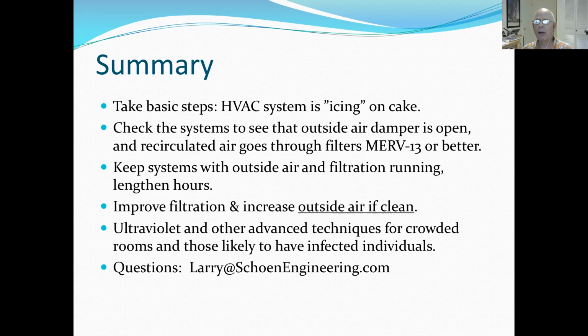And the MERV level for filtration, I gave you that, is MERV 13. And I guess the other component of a decent system is that it runs for at least while the people are in there, and at least for an hour beforehand, and that it delivers air to the room. For instance, if there's a fire damper that got closed and a whole section of the factory floor is not getting air at all, that's a problem. So I would make sure that all the air outlet devices are getting air.